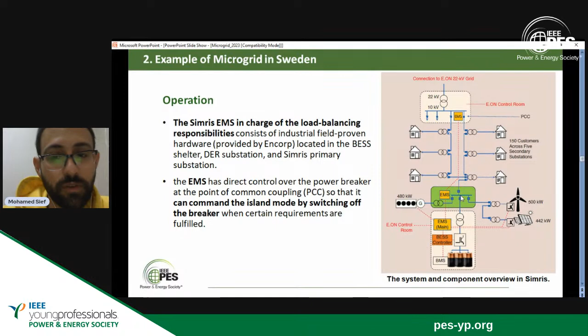The energy management system controls the active and reactive power in order to have no exchange power at the point of common coupling. The PCS controller, which is the controlling system, is running in current source inverter mode. Current source inverter mode means the inverter is working under constant current and operates as grid following. It follows the energy management system.